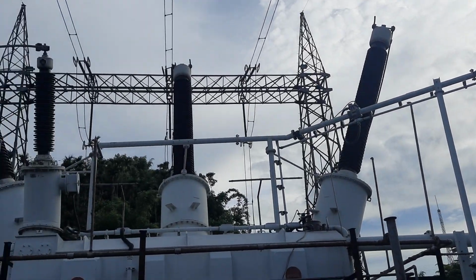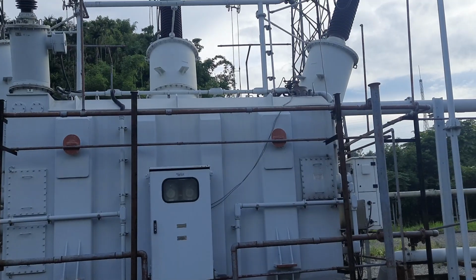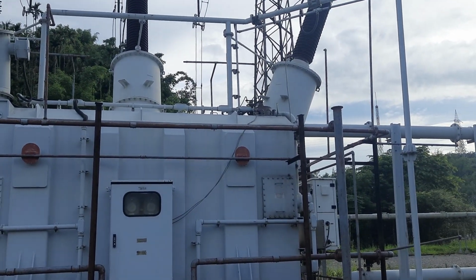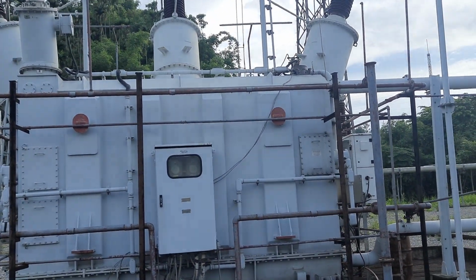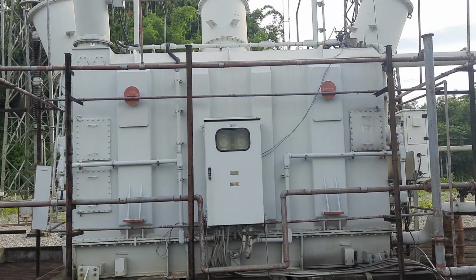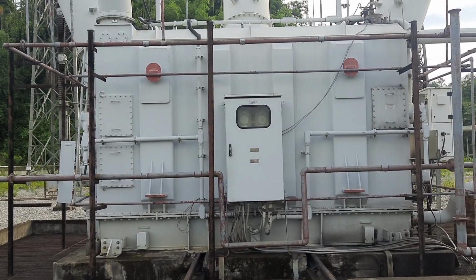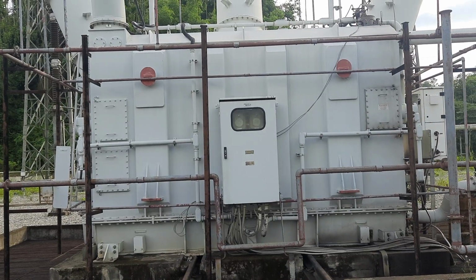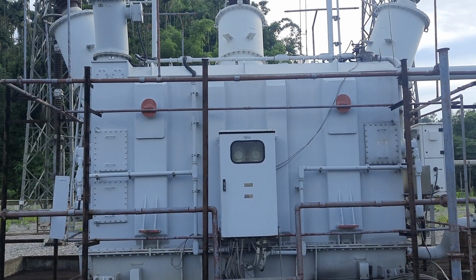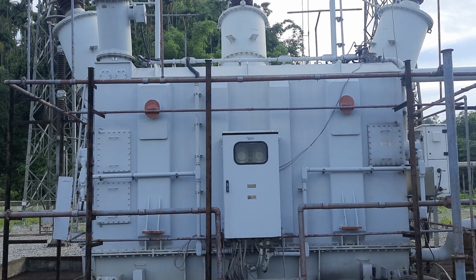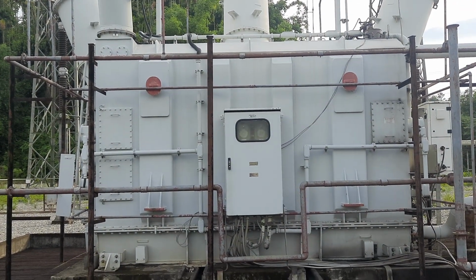And as you know, the Buchholz relay is a gas actuated or gas operated relay. When we go back to the basics, how it works is that when there is a fault inside because of a short circuit, arc fault or winding to winding short circuit, there will be formation of heat, and once the oil heats up, it will generate gases like methane, ethane, ethylene, carbon dioxide, hydrogen.